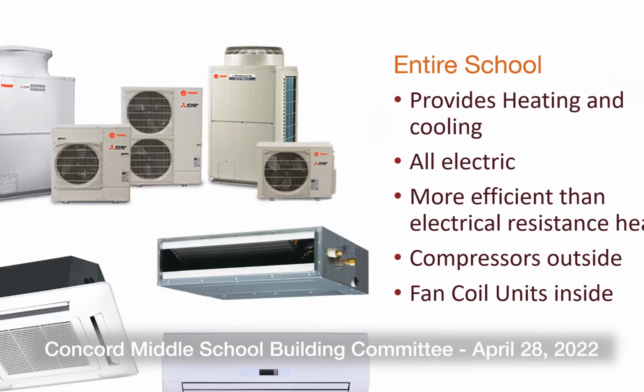Sure. So the VRF system provides heating and cooling, as Steve just introduced, with condensing units outside and indoor units inside. The units in the top picture are what's outside, and the units in the bottom picture are what's going to be inside the building. We're using this system because it provides all the heating and cooling, and it's also all electric, so that's the major draw here. It's more efficient than electric resistance heat—if you've tried to avoid electric resistance heat, VRF systems are generally between 2 and 5 times more efficient, depending on the outdoor temperature. So that's why we're going this route.